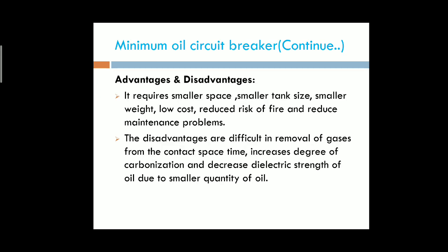Next, coming to the advantages and disadvantages of minimum oil circuit breakers. Minimum oil means that we are using a smaller amount of oil. The main advantage is that the fire hazard is reduced when compared to the bulk oil circuit breaker. The space requirement is also reduced.